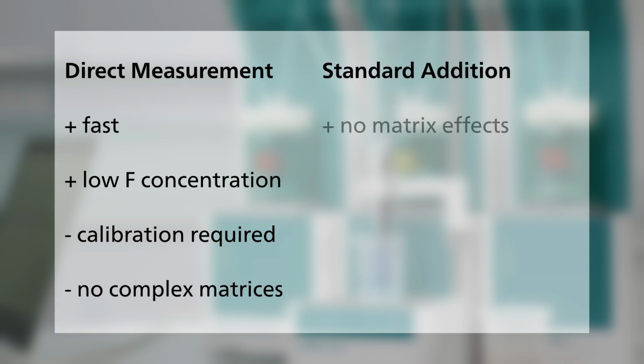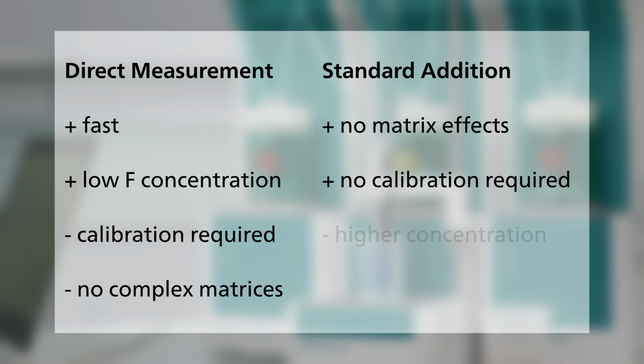In contrast, when performing a standard addition, there is no interference from the sample matrix. Also, no sensor calibration is needed and the sensor is checked with every standard addition. However, be aware that standard addition is not suitable for measuring low fluoride concentrations. Also, a standard addition takes longer compared to a direct measurement.